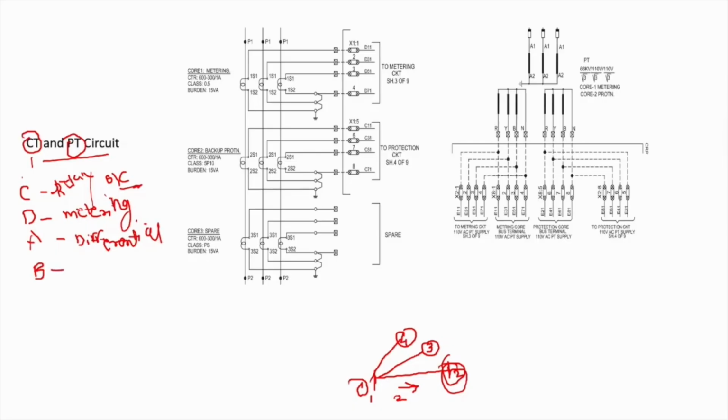The B1 is used for bus bars. Bus bar protection is within this class, right? In bus bar protection, we have to feed the bus bar CT to it. It has to be fed for current measuring. So CD, AB, these are our current ferrules, CT ferrules. You can see them here in the drawing. Look, here it says D, here it says C, right?